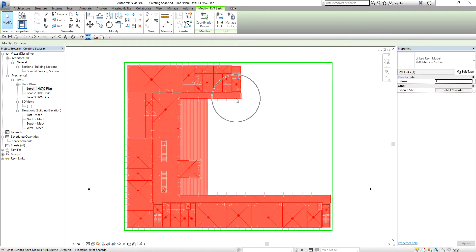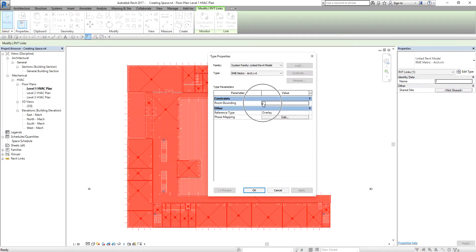The model I have is a linked architectural model. If this is a linked model in your Revit MEP project, make sure that you select the link model and ensure that the room bounding checkbox is selected in the type properties dialog box. Make sure this is checked. This will enable you to place spaces and continue with the analysis, which is otherwise impossible if you don't check this. So if you have a link model in your project and want to make spaces, always make sure room bounding is checked.